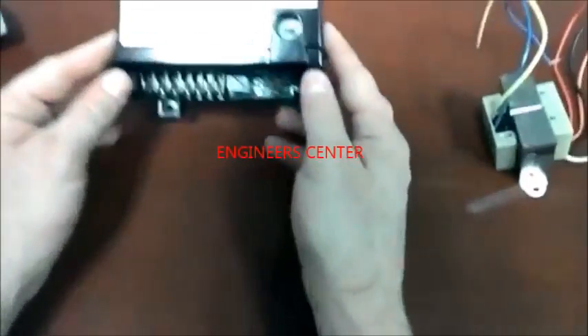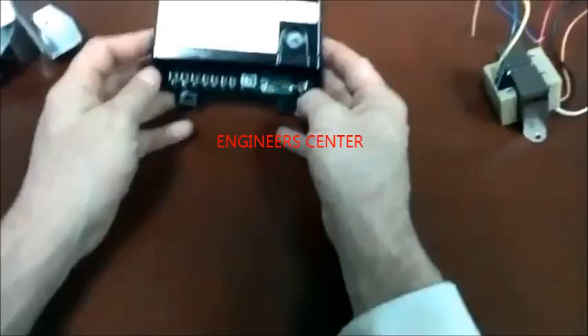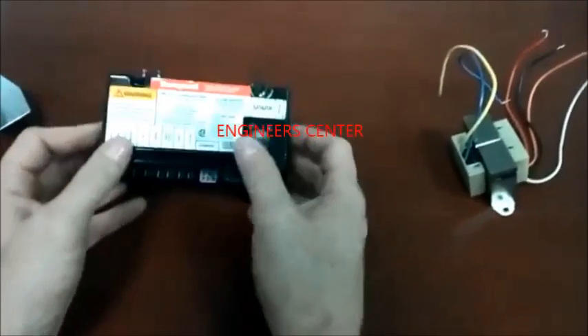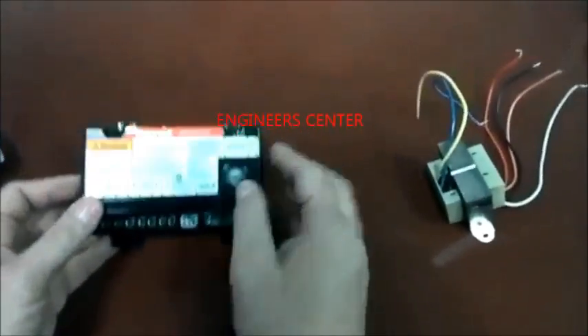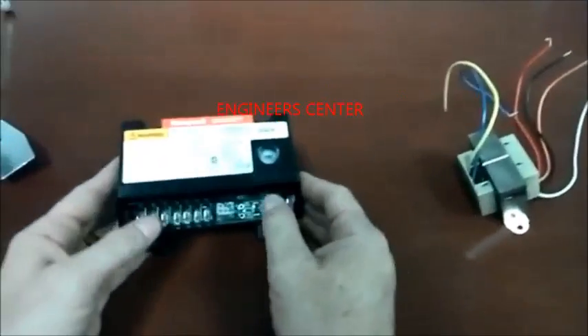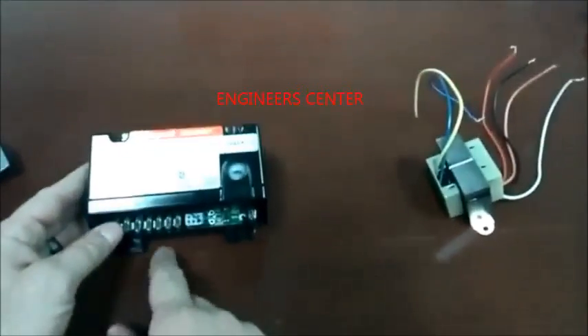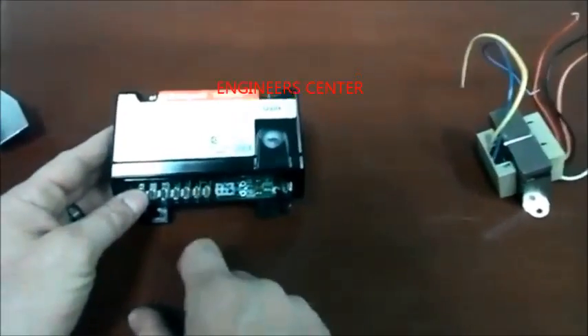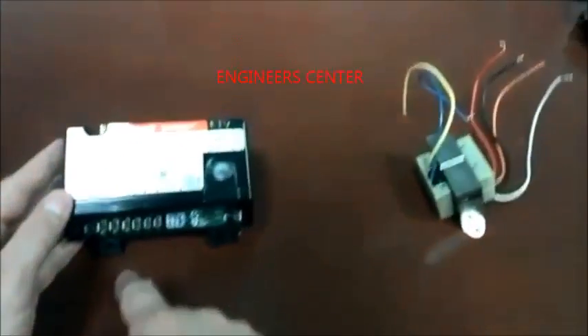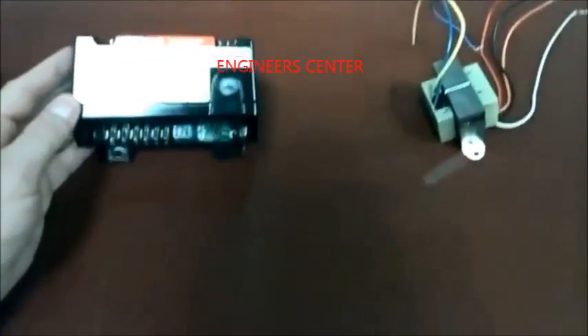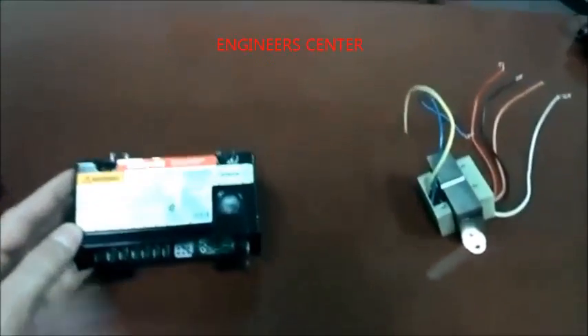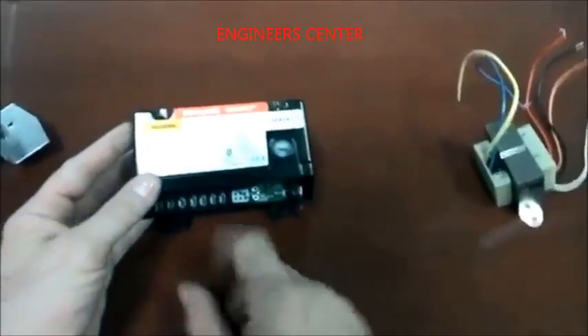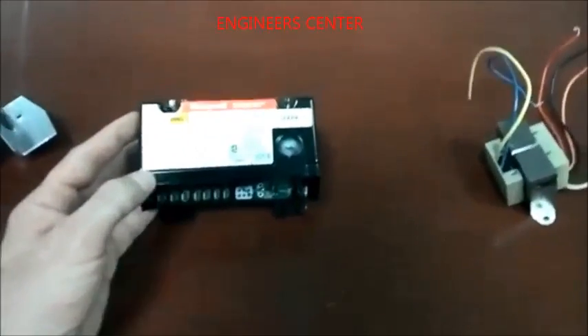And, you know, moving on, we have an ignition module, or circuit boards would be the same thing, but these are just a series of relays. It's just on the board, a whole bunch of them. And so if you were to, for instance, give this thing 24 volts, you're essentially giving this thing power, and so it's going to respond to your 24 volts. You have to know its sequence of operation now, because I would know that it would start sparking, and then it would energize the pilot valve. You just have to know how something's going to work.